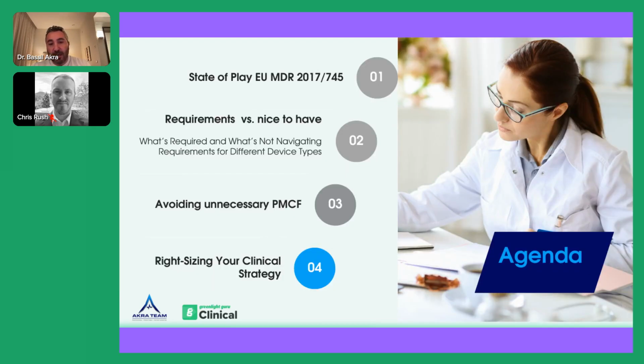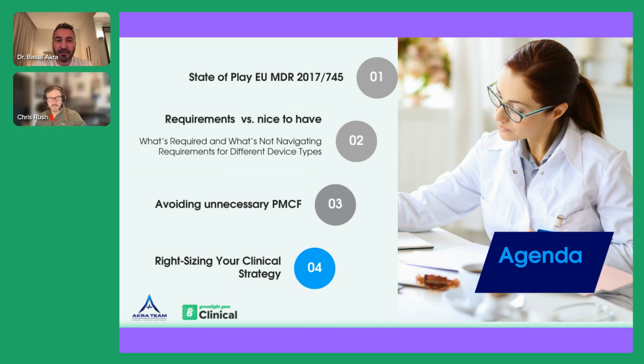Now, as I mentioned, there are pathways where you can go through clinical data collection, some others which can be relying on equivalent devices, some devices which can justify they have sufficient evidence because they are well established, or they are actually devices which have sufficient data based on the MDCG 2020-6 criteria. Some devices don't need clinical data at all because from their characteristic, they don't require clinical data. But for some devices, you would need also clinical data.